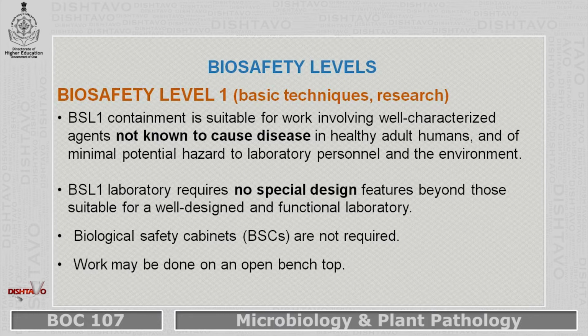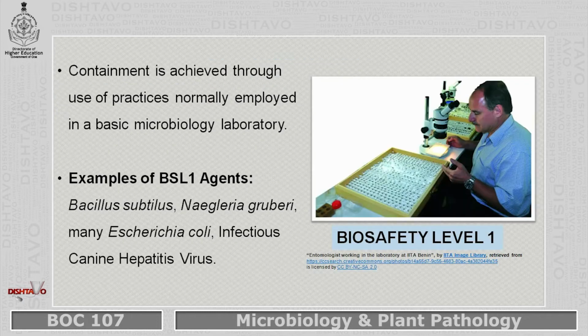Coming to biosafety level 1, containment is suitable for work involving well characterized agents not known to cause disease in healthy human beings and of minimal potential hazard to laboratory personnel and the environment. A biosafety level 1 laboratory requires no special design features beyond those suitable for a well-designed and functional laboratory. Biological safety cabinets are not required when dealing with these agents. Work may be done on an open bench top. Containment is achieved through the practices normally followed in a basic microbiology laboratory.